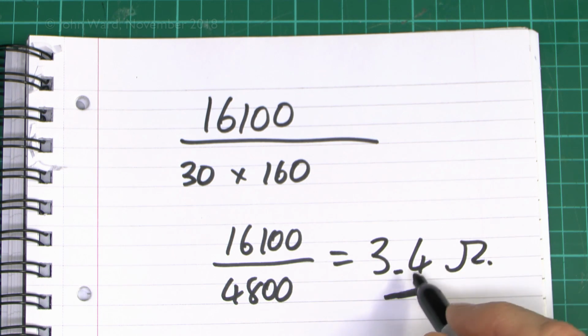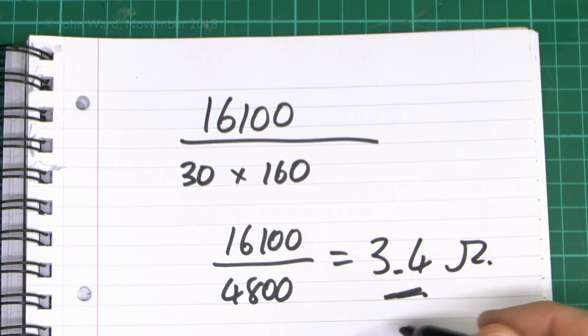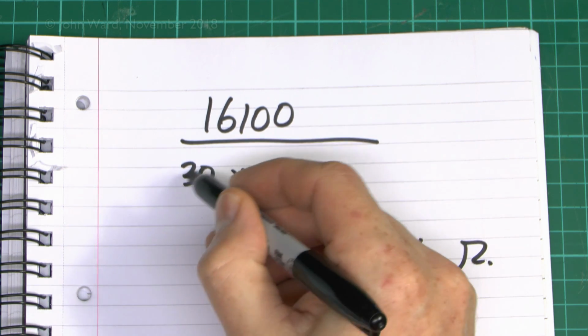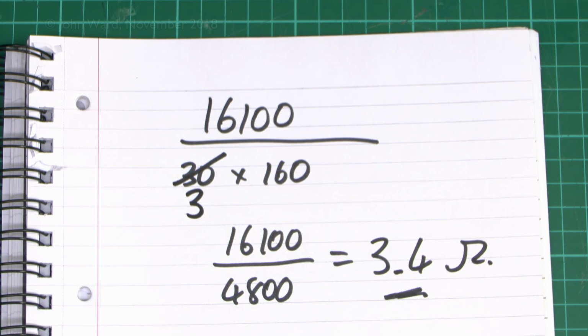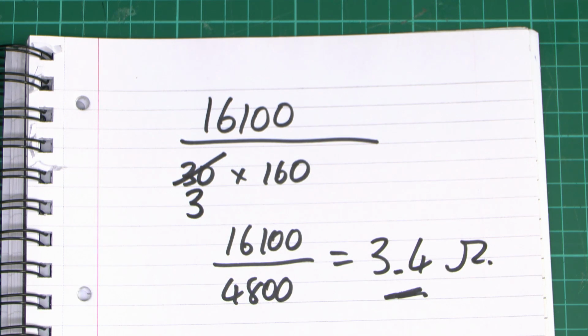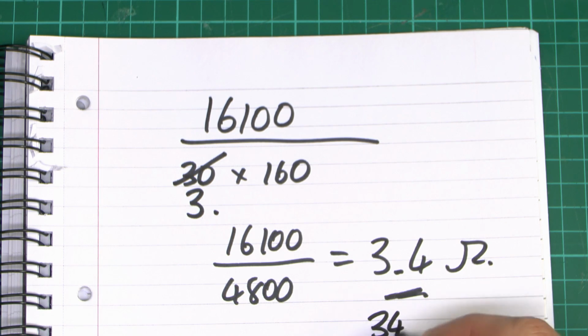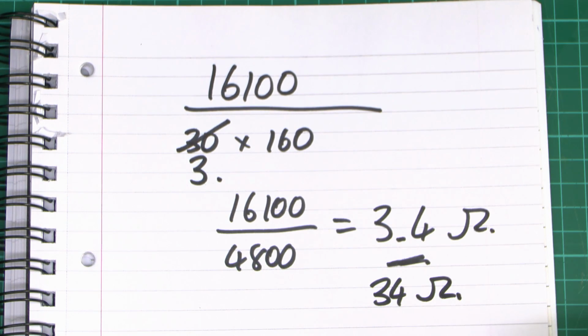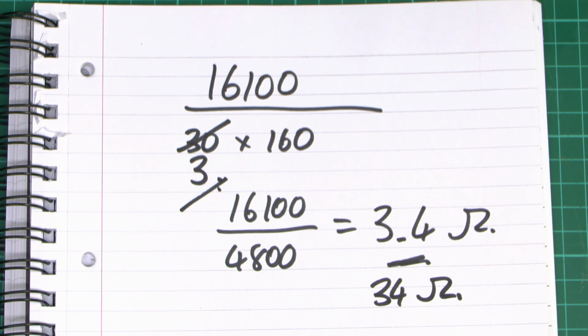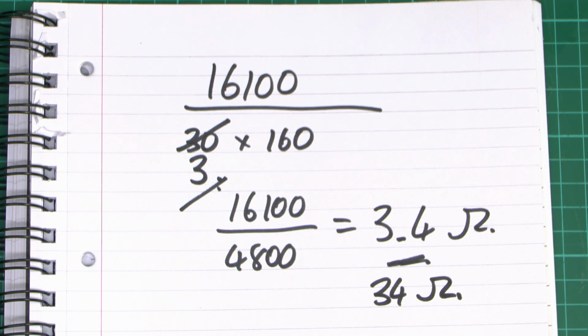And in fact, to get anywhere near a credible value, which would be tens or 30s of ohms or so, we would actually have to go not for a value of 30, but for a full load current for the installation of only 3 amps. And of course that's not going to happen anywhere, because clearly the vehicle itself is more than that. If it was 3 amps, that would give us a total resistance of 34 ohms, which at least is reasonably realistic. Certainly possible to actually get somewhere near that. But again, you're not going to have 3 amps full load for the entire installation, including the vehicle. Charge up your Tesla model, whatever else, with a 3 amp load, it's going to take 10 years to actually do so.